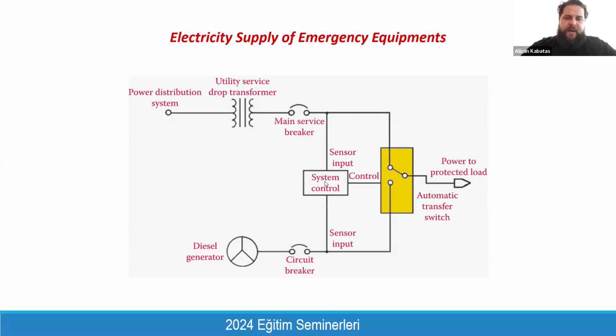And also the emergency equipment should be fed by both main electricity and also the diesel generator. And that's why it is important to find a place for the automatic transfer switch when you are designing a room for fire pumps, for pressurization fans, or for smoke extraction plants. This is a panel, and we need to provide it within the room so that it can feed the emergency equipment without having an interruption.